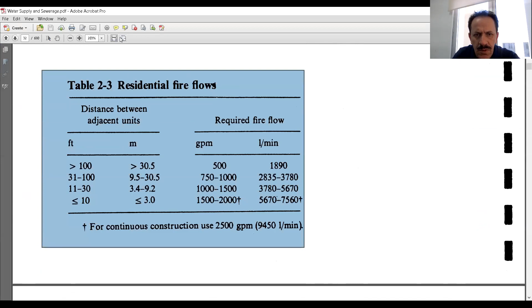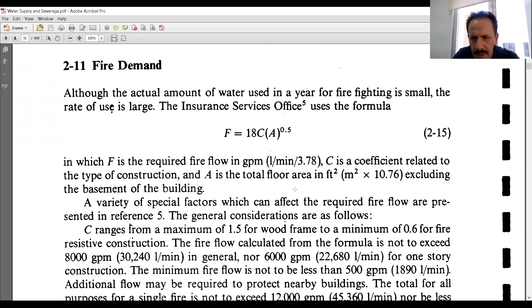I think it was in the slides as well. Yes, this is the ordinary one. For ordinary buildings, we use the value of C as 1, and for wood, we need at least 1.5, so we substitute 1.5 for 1. A is substituted in square feet, C as a coefficient without any factor, and the 18 is fixed. So I get the value of F, in gallons per minute, which is the flow this fire needs.